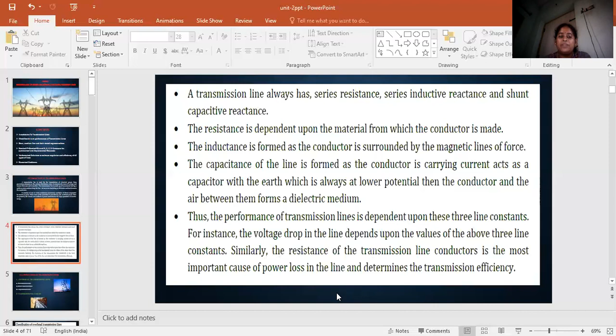The resistance depends on the type of material used in the conductor, the area of cross section, and the length of the conductor. The inductance is formed as the conductor is surrounded by magnetic lines of force. The current flowing through the conductor experiences magnetic lines of force around the conductor, on the outer side and inner side of the conductor also. The capacitance is also formed as the conductor carrying current acts as a capacitor. Mainly, the power loss: the resistance of the transmission line conductors is the most important cause of power loss in the line. Using that, we determine the transmission efficiency.